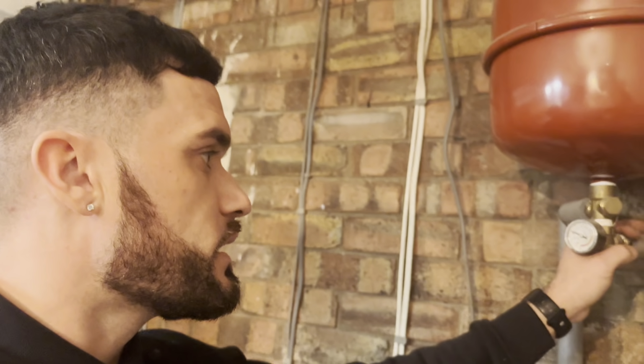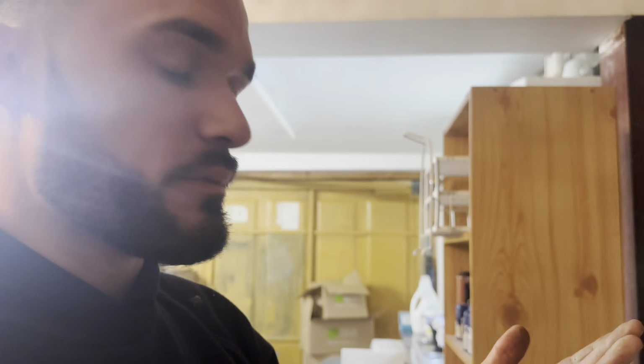I'm going to put a new head on, I've got one in the van, just put it onto that body, unblock that. We'll get some chems in, get filled up, and then that's the first port of call. We're going to need to do this because the pump is not performing at its best, so this could be playing a part as well while there's not enough heat getting on the building, but this potentially could eliminate a lot of factors. I think once them chemicals go in, it'll aid lubrication of the system and allow water to be forced to a certain place, so we'll pop to the van and see what we've got.